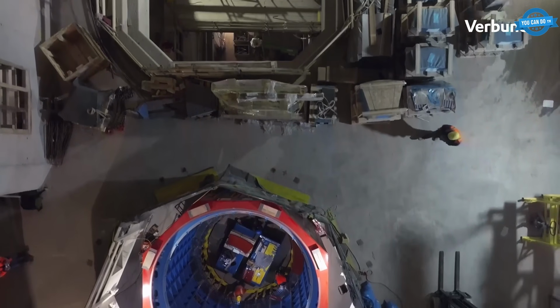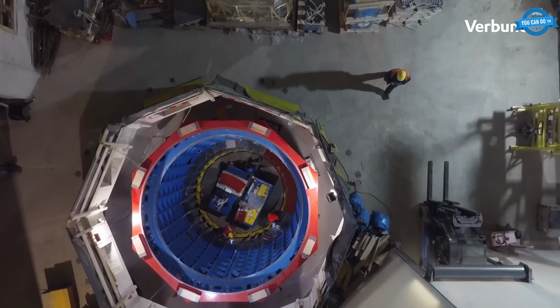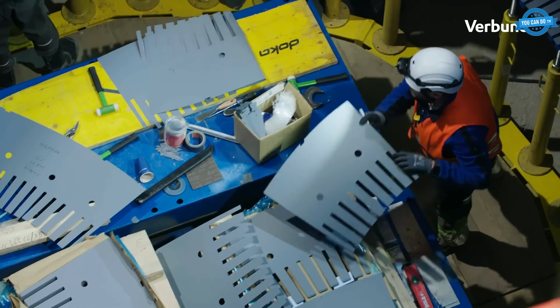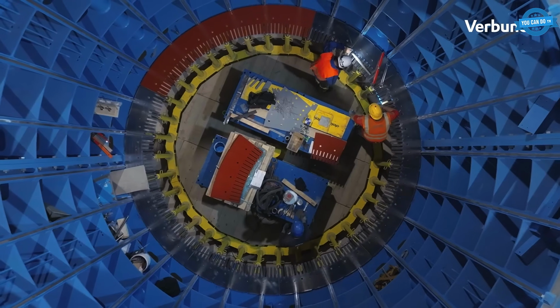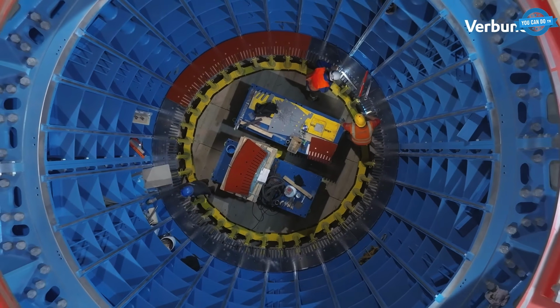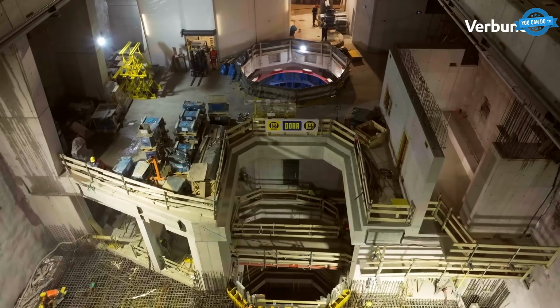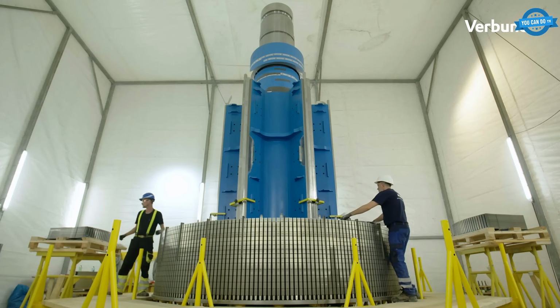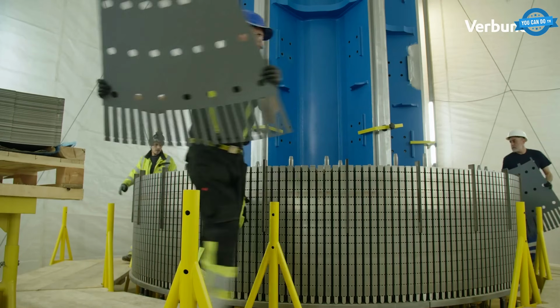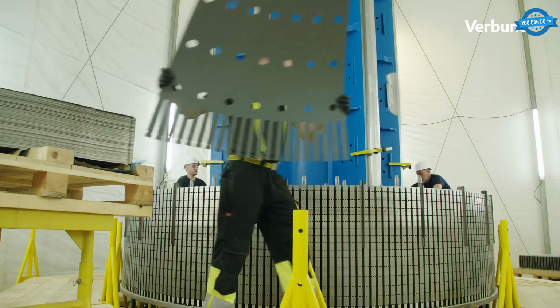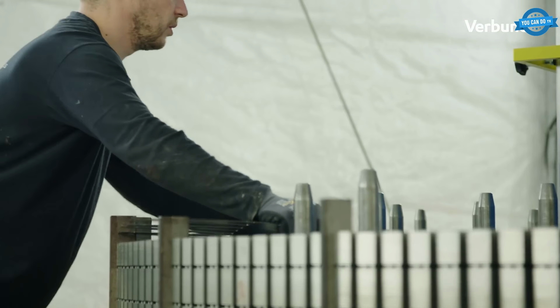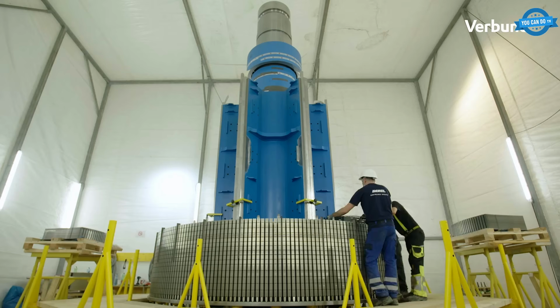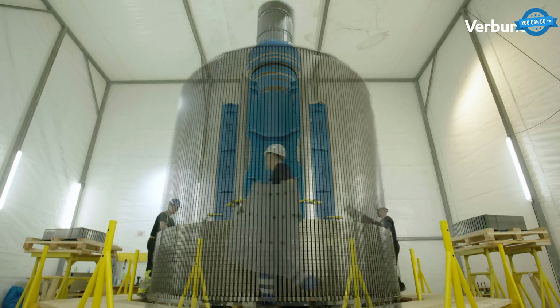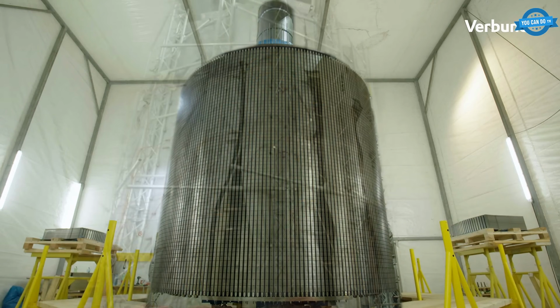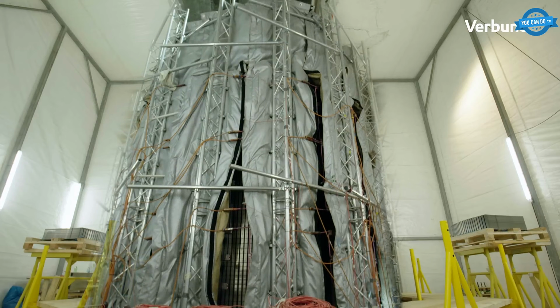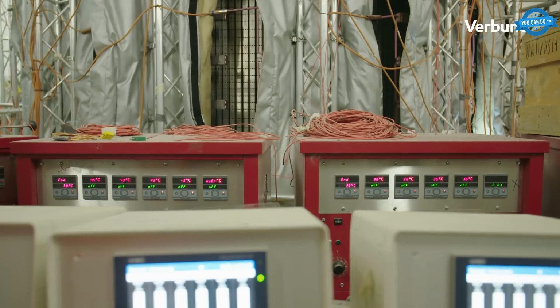Building a 480-megawatt machine inside a mountain is one job. Hand stacking 90,000 dynamo plates, each 0.5 millimeters thick, to build the stator that converts water pressure into electricity is another. Fitters begin layering the stator and rotor of Machine 1. The laminated structure aligns magnetic fields for higher efficiency. The rotor needs 6,500 layers around the central shaft, nearly 3 months of work, with the steel pack heated repeatedly to 160 degrees and pressed before being shrink-fitted onto the shaft.